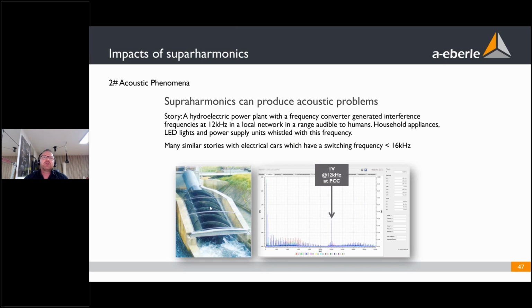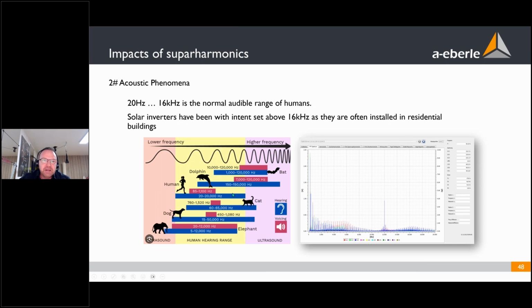The next problem which we could have with supraharmonics could be an acoustic problem. People can hear between 20 hertz and 16 kilohertz maximum. The limit depends on how old people are. Younger people can hear a little bit more and older people a little bit less. But in this range, we expect that people can hear some noise. Therefore, some manufacturers put the switching frequency of the power electronics a little bit higher, so that you never have an acoustic problem.